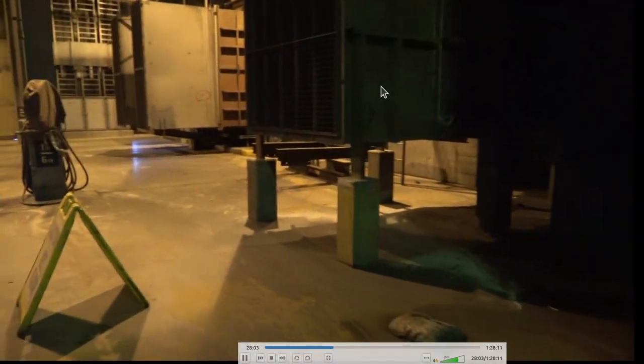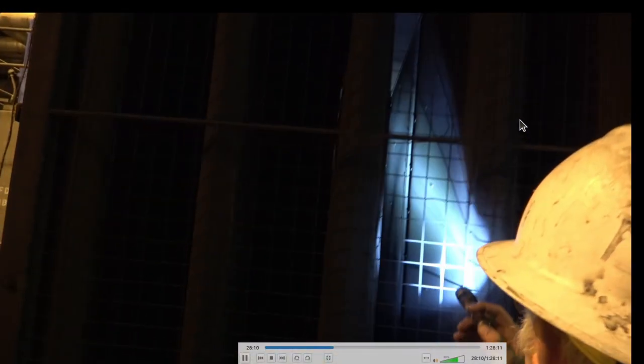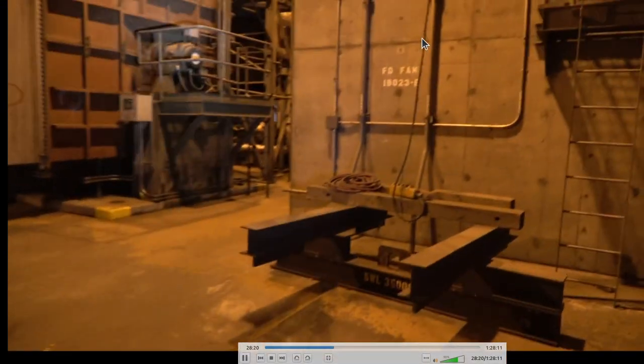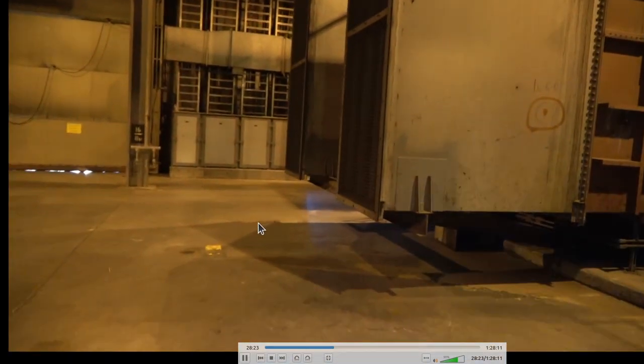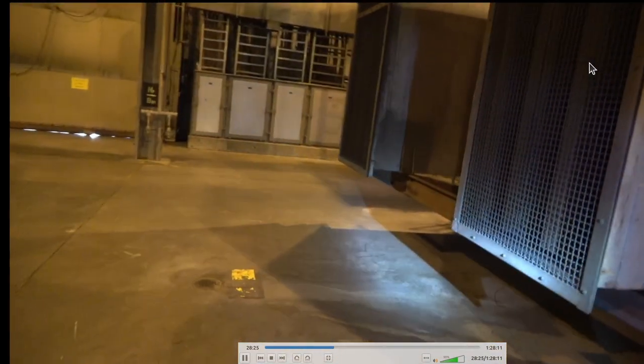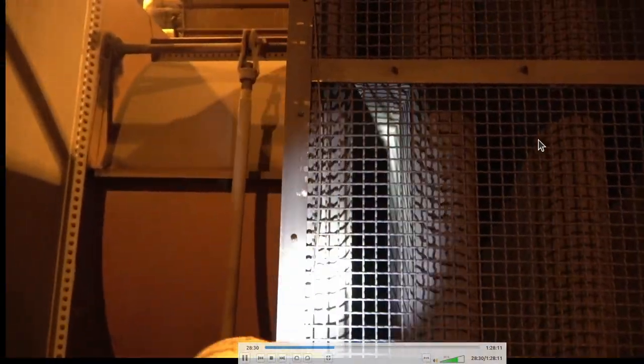This is the other fan room — just like the other one. They pull quite a bit of air through. They have a little lube oil system in the back — the oil is cooled and filtered, sent back into the bearings. The bearings have slinger rings on them, and also sprays that dump oil on top of the bearings to make sure there's good lubrication.